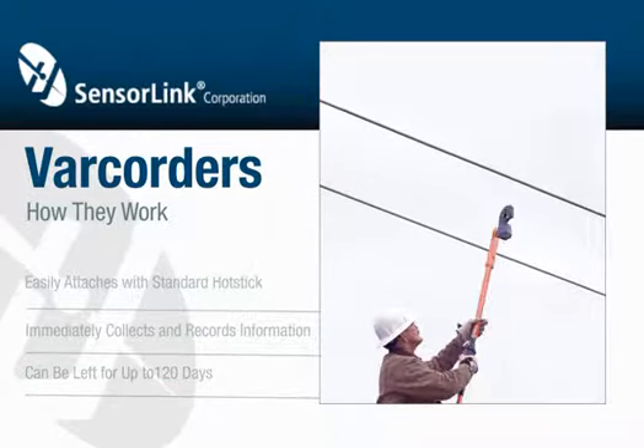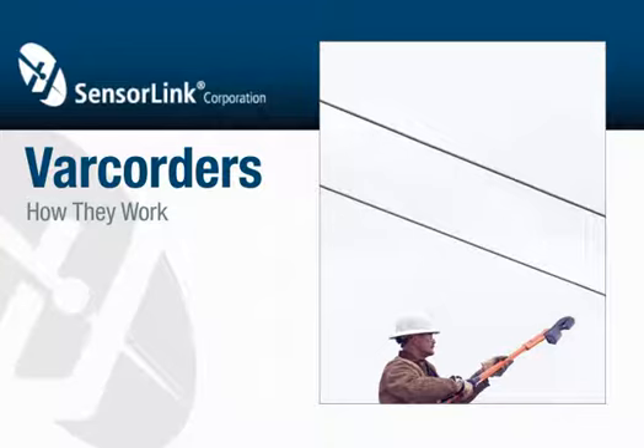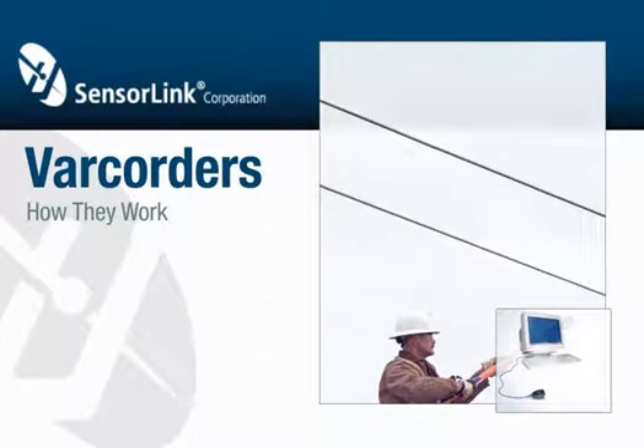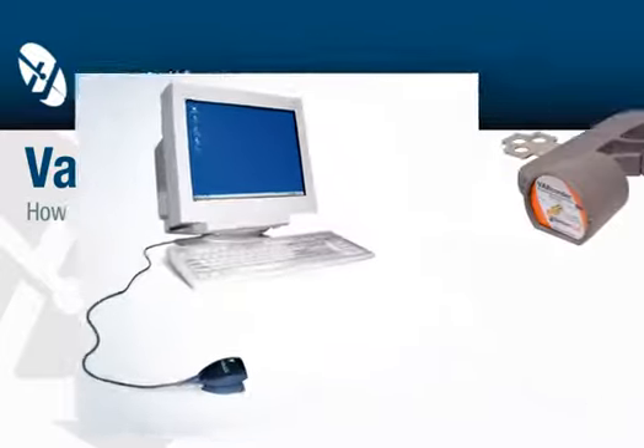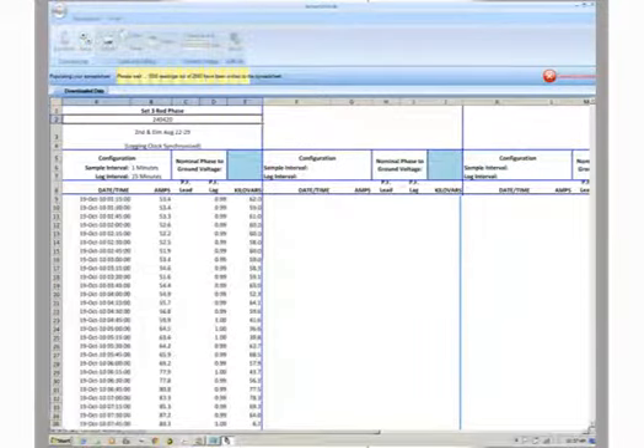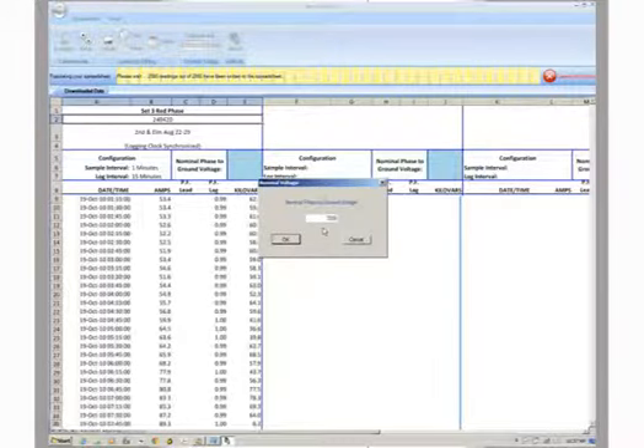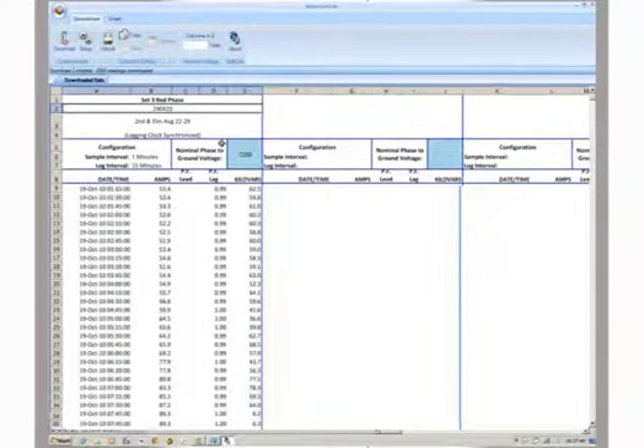with captured data. The Varcorder is now ready to download its data into your PC through SensorLink's SoftLink software. Simply position the Varcorder in front of the infrared serial port and double-click the SoftLink icon on your PC. Select the download icon, and SoftLink will download the data from your Varcorder. Once the data is downloaded, enter the nominal phase to ground voltage for each Varcorder, and the spreadsheet will calculate the kVARs. Data from multiple Varcorders can be downloaded into the same spreadsheet.